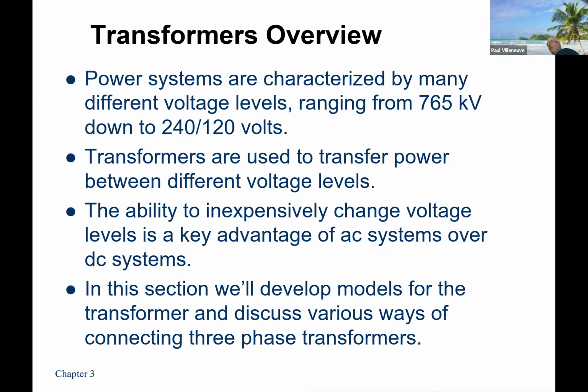The other thing about it too, remember how we talked about three-phase systems? Well, in reality, we have three-phase transformers, but they are not really three-phase transformers. There are three single-phase transformers that we will connect in delta or Y to make a three-phase total transformer, okay? Now, you can buy those in one complete package. So you see three bushings and the three individual phases are interconnected inside the transformer. But those are for smaller transformers. If you get to really big transformers, like pushing 800 MVA in size, those usually can't be three-phase transformers. Anybody want to guess as to why?